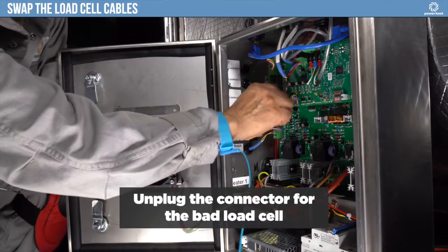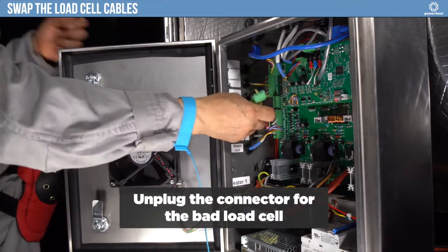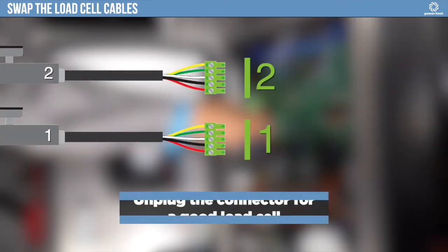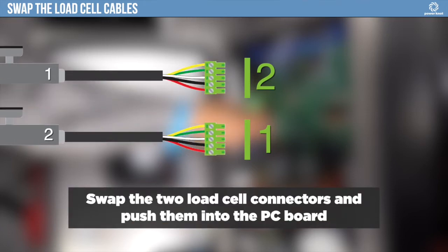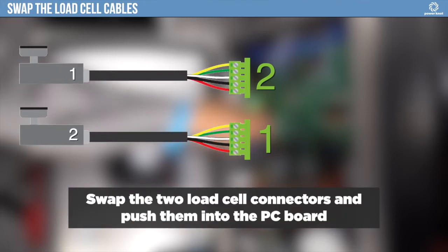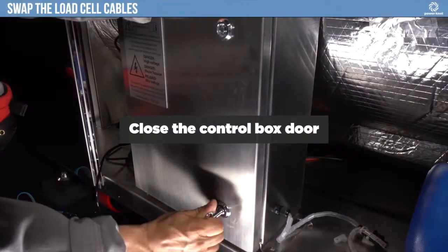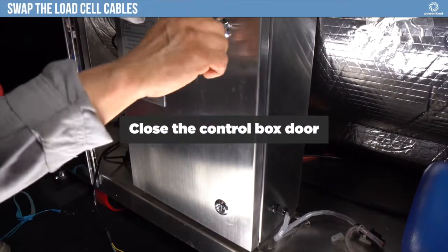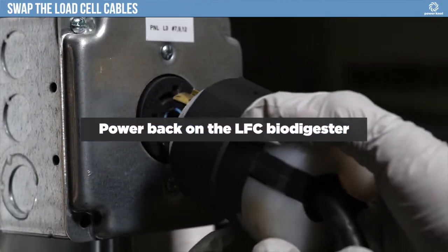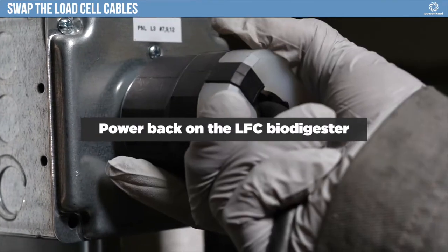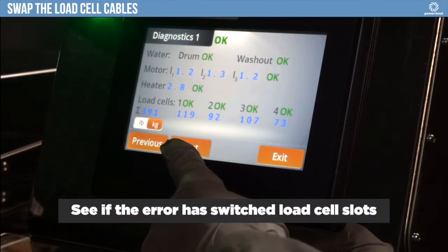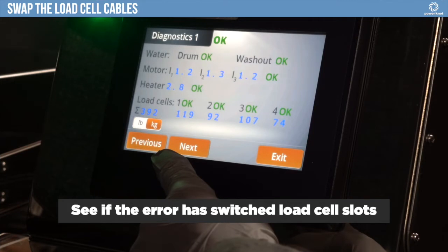Unplug the connector for the bad load cell. Unplug the connector for a good load cell. Swap the 2 load cell connectors and push them into the PC board. Close the control box door. Power back on the LFC biodigester. See if the error has switched load cell slots.